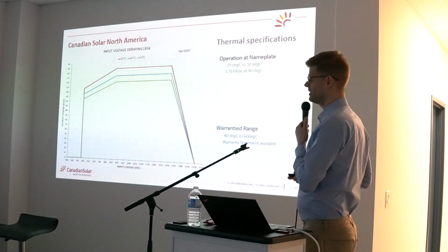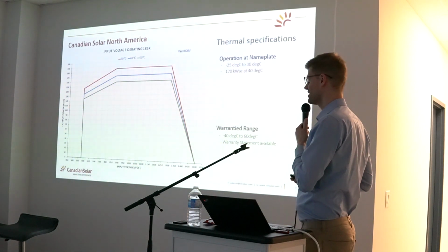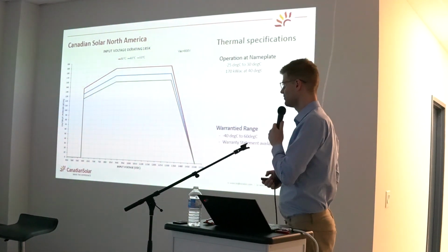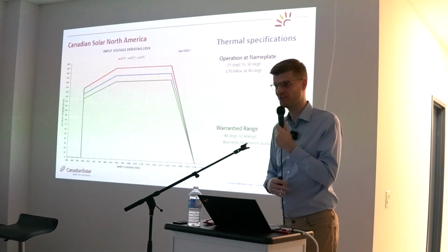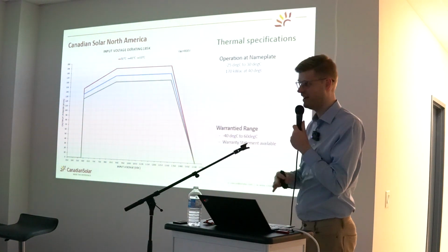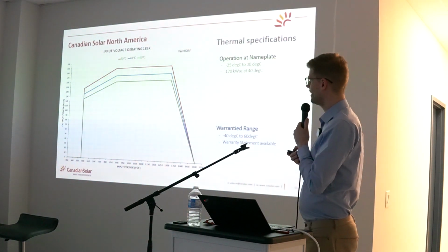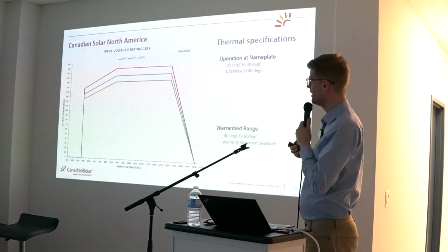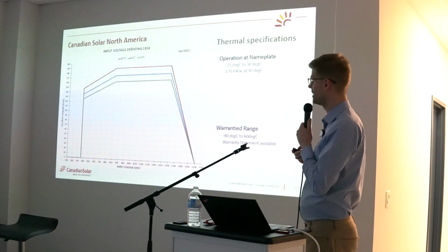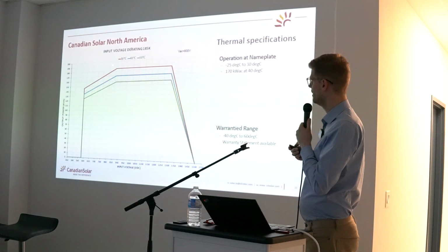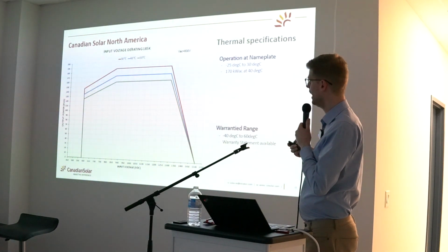Thermal specification, that's a big topic, not necessarily for Canada, but in the States. For Canada, it's a topic for low temperatures. In the US, it's a topic for high temperatures. In Canada, the 30-degree mark here for that 185 kilowatt gives you the full nameplate output power up to 30.